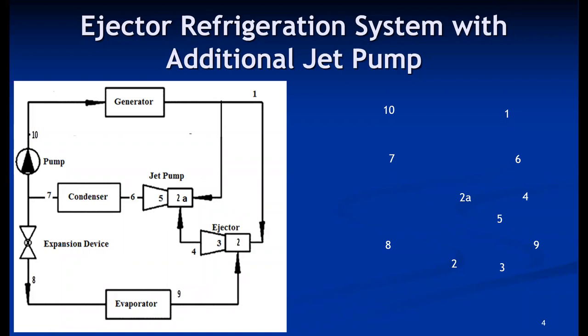The first modification is the ejector refrigeration system with an additional jet pump. If the basic ejector refrigeration system cannot generate the required pressure, we can use multiple ejectors — this is also called a multi-stage ejector refrigeration system, because ejectors are connected in series. This is especially useful when a higher condensing temperature must be maintained, for example with air-cooled condensers in summer where the cooling medium temperature rises and it becomes difficult to maintain a low condensing temperature.